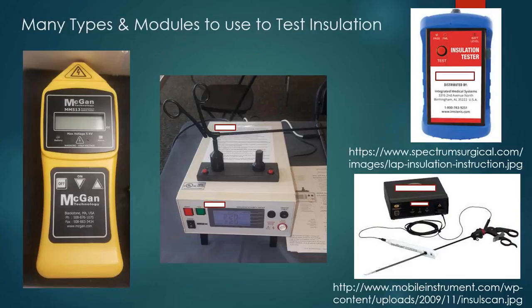Some repair vendors may provide an insulation tester to the customer at no cost, but make sure the tester meets your instrument device inventory as well as your staff's educational needs for the unit. For example, if you have a tester that just tests laparoscopic instruments, but you have bipolar forceps or cords, how is that going to be done?